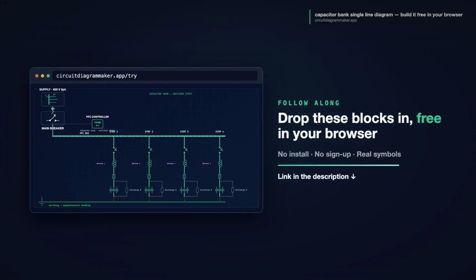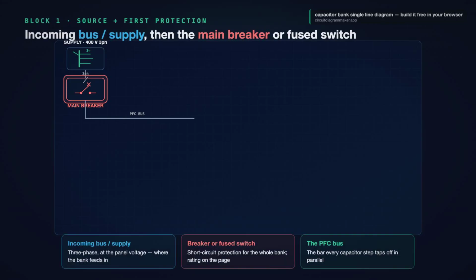Block 1, the incoming supply, the main breaker, and the bus. On the left, the feeder comes in, your three-phase supply at the panel voltage. Right after it comes the main protection, a circuit breaker or a fuse switch sitting across the line. Its job is short circuit protection for the whole bank. If a fault dumps huge current, this is what clears it, and its rating goes right on the page. From there, the line lands on the PFC bus, the bar every capacitor step taps off in parallel. Supply, breaker, bus. That is where the bank begins.